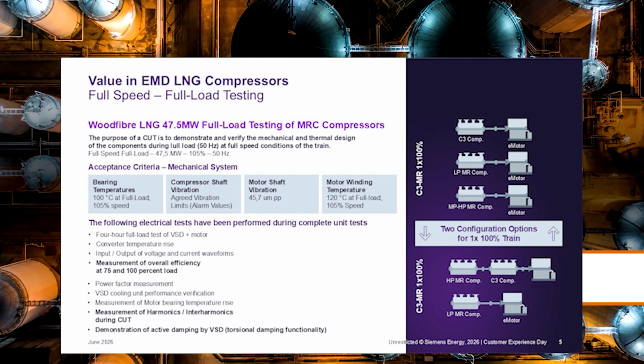That was as much of a full string test as you could possibly get. Along with that, we were able to test our converter temperature rise within the variable speed drive, input and output waveforms, measured overall efficiency, and also took measurements of the power factor and what was going on with some of the harmonics and interharmonics.